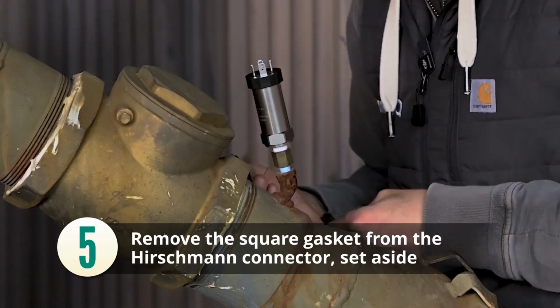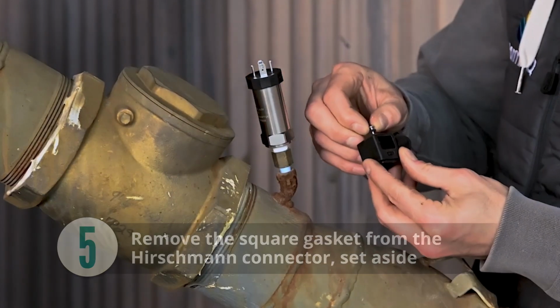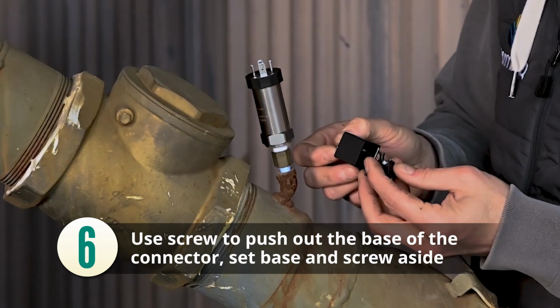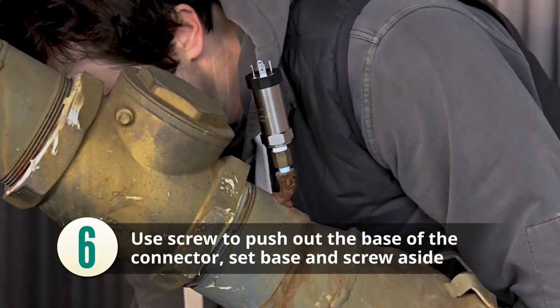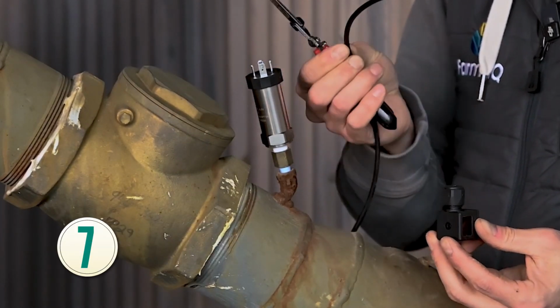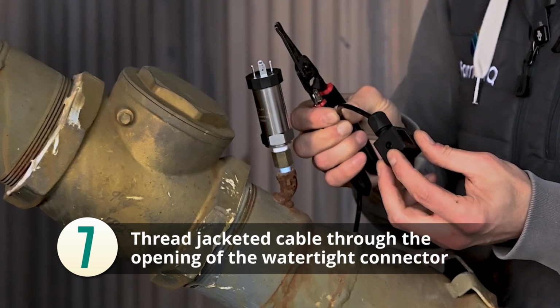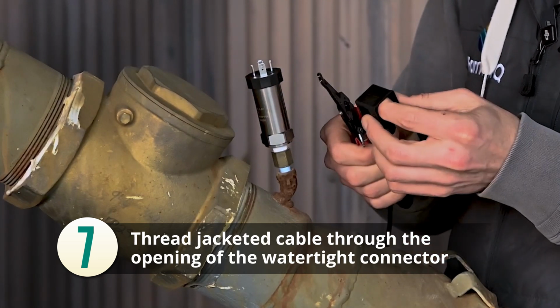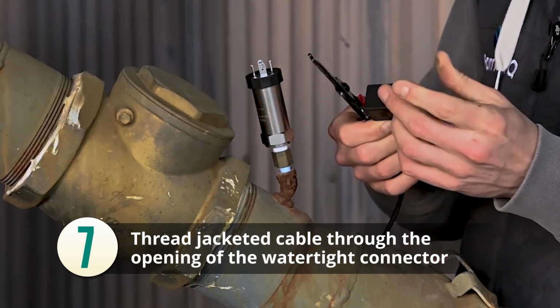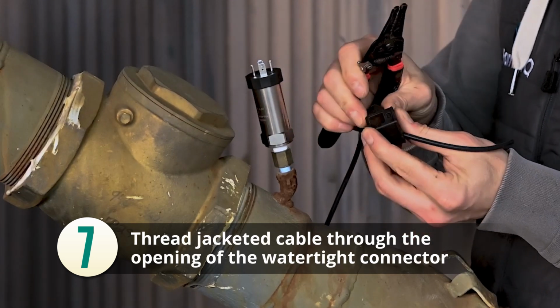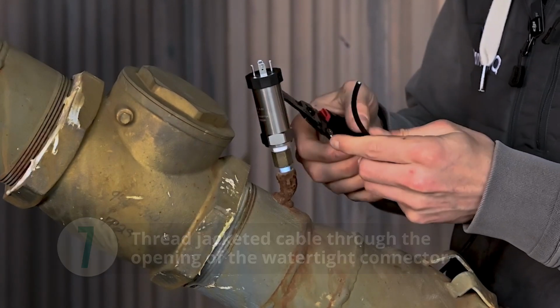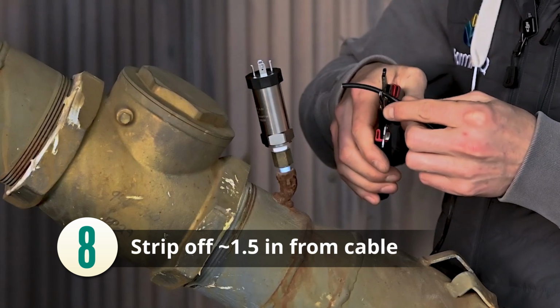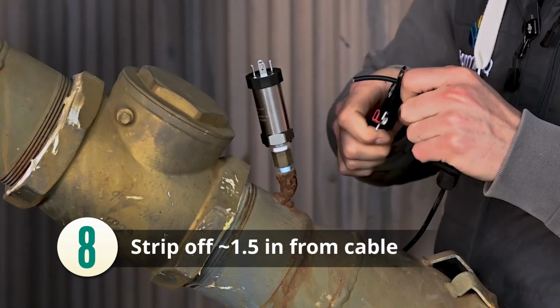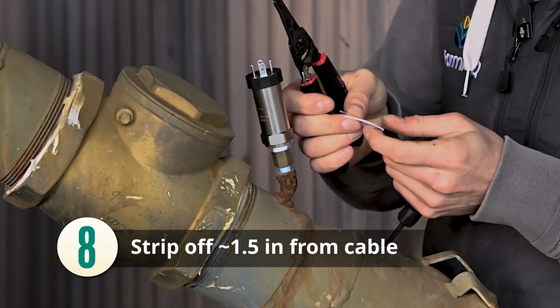So now we're going to take the top of our Hirschmann connector, save the square gasket. You can use the screw to push the base of the connector out. We'll set that aside and the screw. Okay, so the first thing we're going to do here is thread our completely jacketed cable through the opening of the connector and pull it out. So now the cable is going through this watertight connector here. We'll go ahead and strip off about 1.5 inches of the insulating jacket of the cable, and then you have your black, red, and white wires inside.